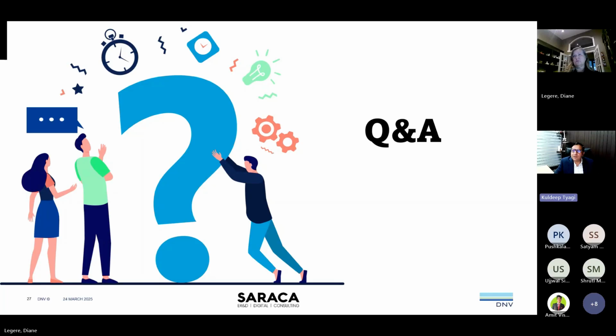How can manufacturers of Class IIa and certain Class IIb medical devices navigate the specific regulatory challenges under the EU MDR? And what are the key strategies for ensuring compliance? Yeah, so I'll go back to my prior comment around planning: you need to develop a regulatory strategy that takes a look at what you had under MDD.